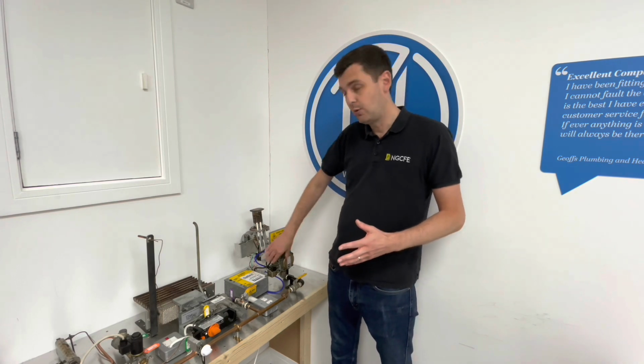The reason it's called a zero governor is because the fan draws the gas through the unit, so it sucks the gas, creating a negative pressure. So if you were to even attempt to take a burner pressure, the reading you would get would be less than zero. It'd be a negative pressure you'd get. So how it works is the fan kicks in and draws both gas and air in at a predetermined ratio and mixes it before it gets to the burner point. Once it gets to the burner point, then we move over to the flame rectification side.